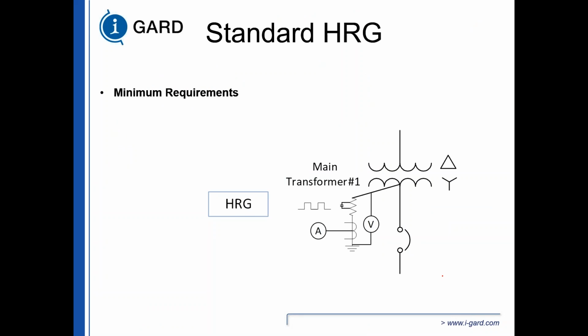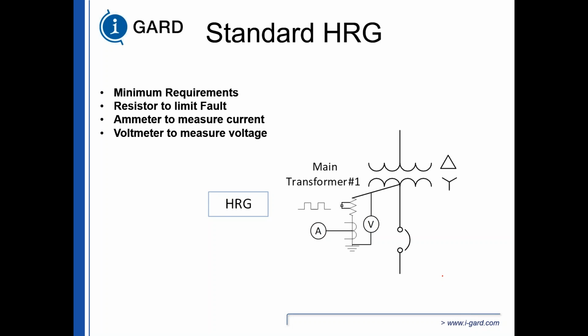So standard HRG, the minimum requirements: you need a resistor to limit the fault current. And believe me, we've seen a lot of systems. I've seen people use stove elements as resistors to create high resistance grounded systems. You need an ammeter to measure the current, and you may or may not use a voltmeter to measure the voltage. You should have a pulsing contactor to help you locate where the fault is. Now, this alone will allow you to have your system maintained constantly so that you don't have to shut down when you have a ground fault. It helps you locate where the fault is, and you have an arc flash mitigation technique with standard HRG. That's a given. We can have this.